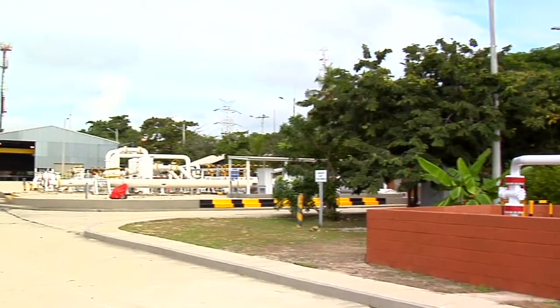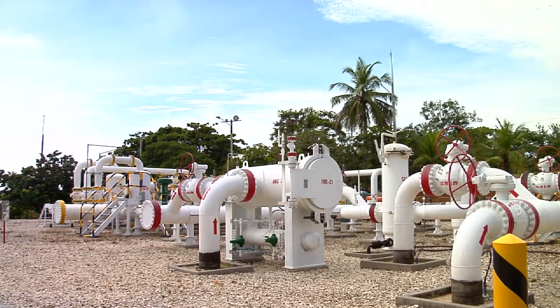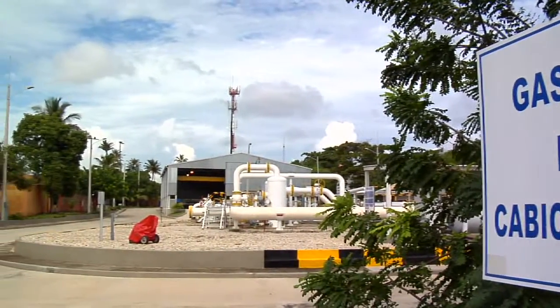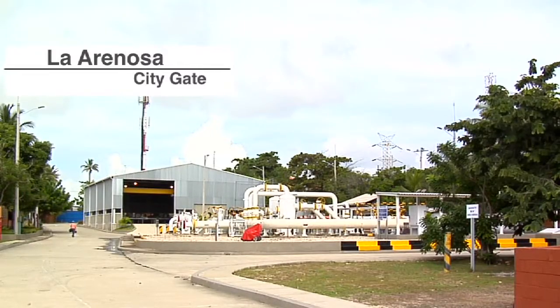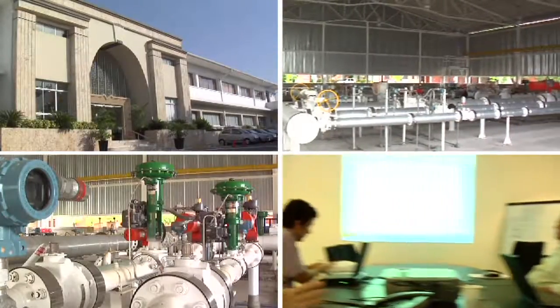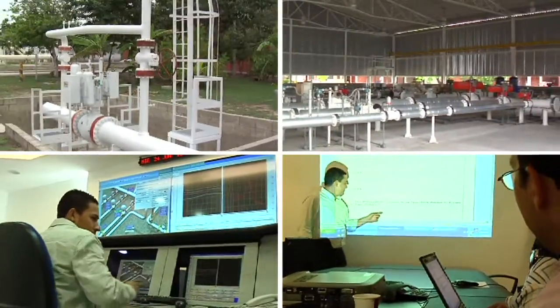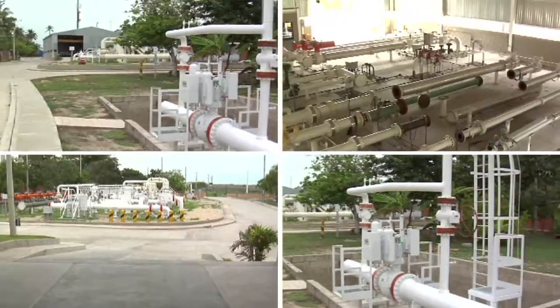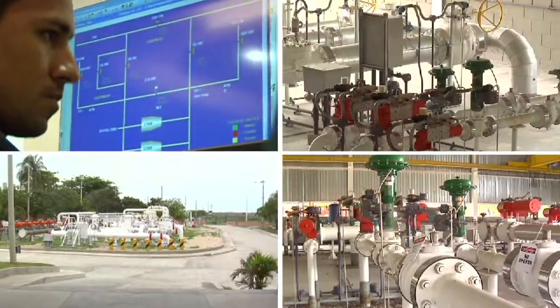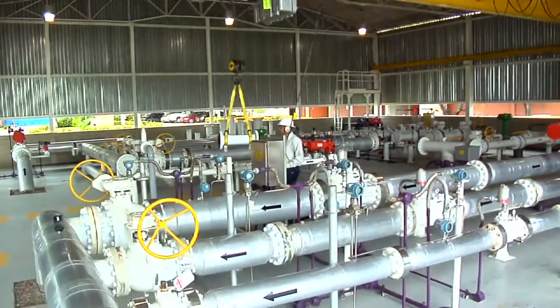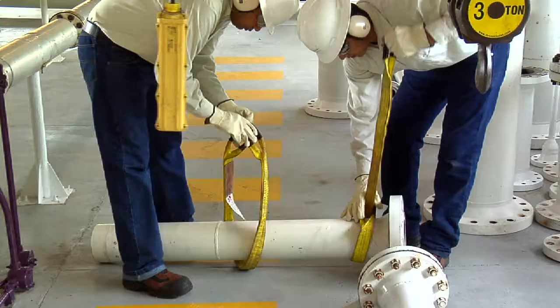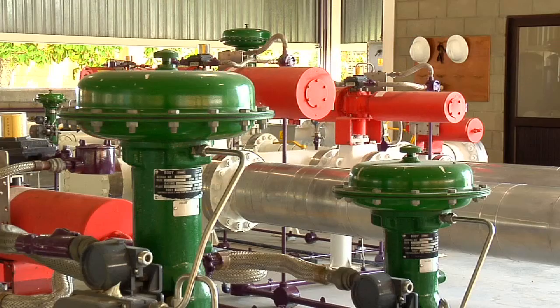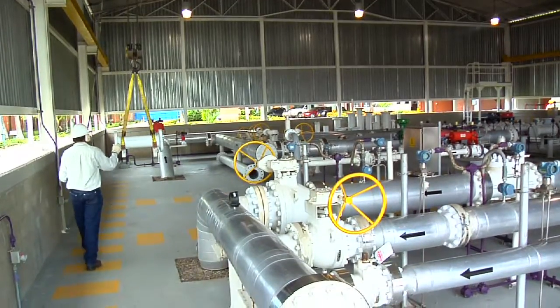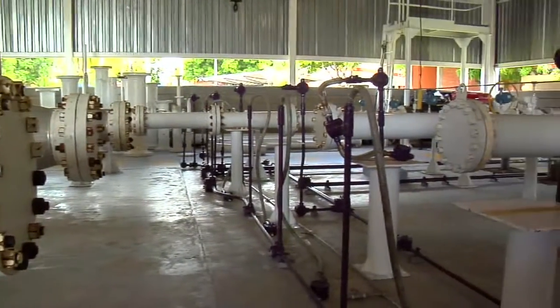The city gate, La Arenosa, is located on the banks of the Magdalena River and supplies natural gas to the city of Barranquilla. In 2007, Promigas began to design a metrological meter testing laboratory that takes advantage of available natural gas. The result, 1 year later, was the standing up of the first gas meter calibration facility in Latin America, which uses natural gas at high pressure as calibration fluid.